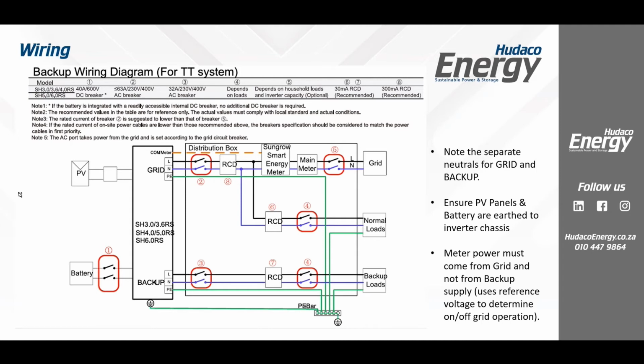When we first did the installations, a couple of them, we thought, well, let's take the power from backup. That way the meter will always have power, right? The problem then is it doesn't know that the grid has fallen away because the voltage reference remains. So the relay keeps opening and closing because it doesn't quite know that it's supposed to be in off-grid mode. Okay, so very important, please power this from this line, not from this line.